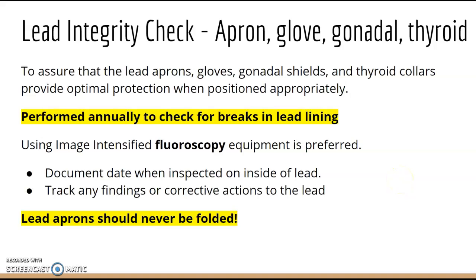Lead integrity checks include all types of lead protection: aprons, gloves, gonadal shields, and thyroid shields. All shielding must be tested annually using fluoroscopy equipment to check for cracks or breaks in the lead lining. Never fold your lead apron. Each apron should have a documented inspection date on the inside, or a barcode that can be scanned to track when it was last checked.